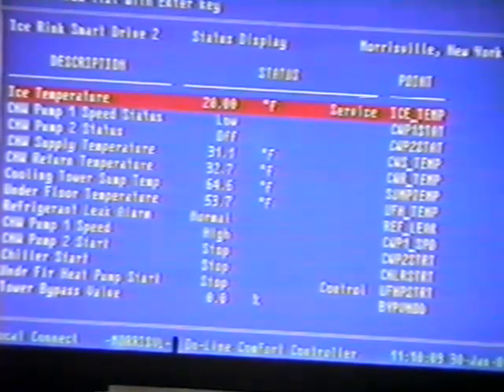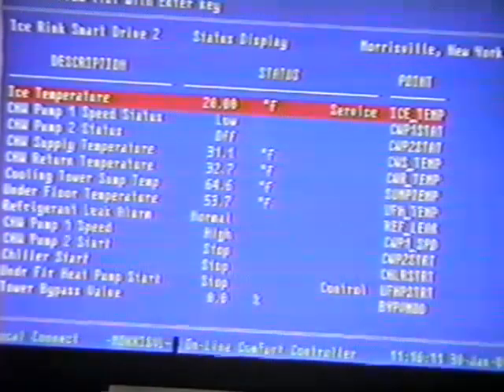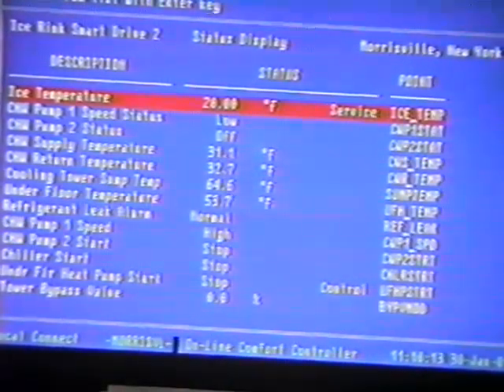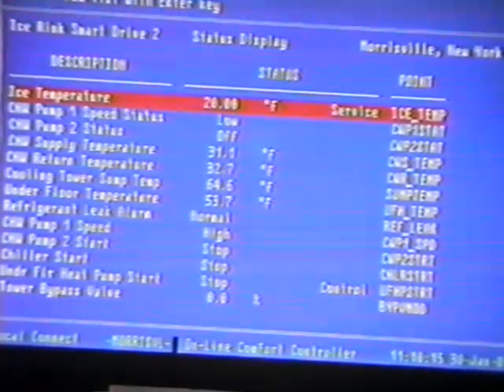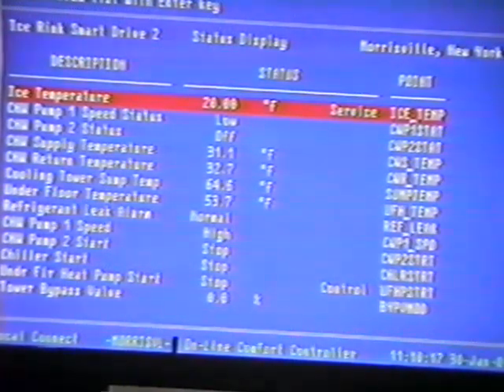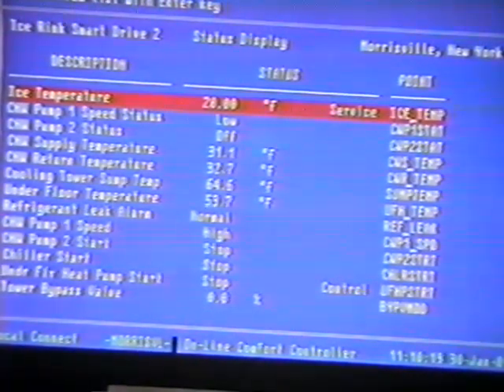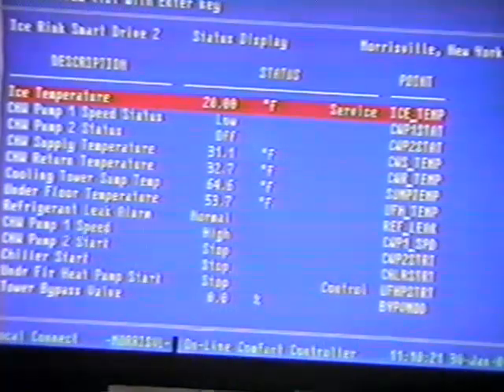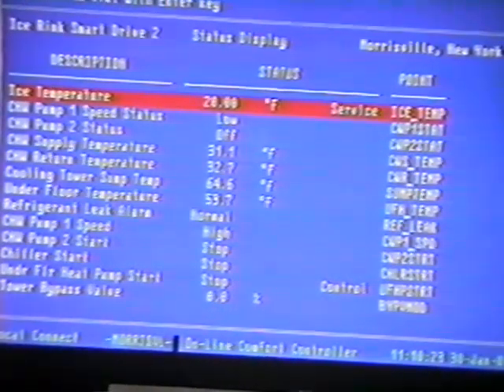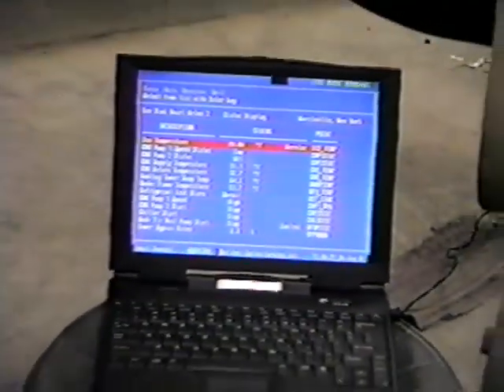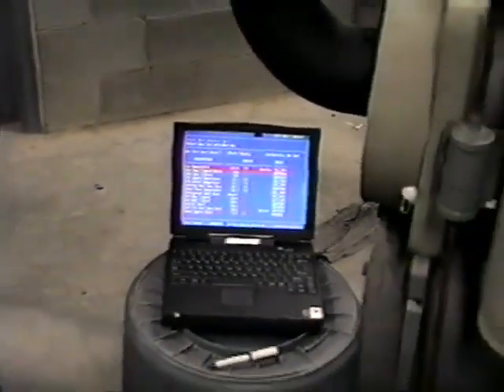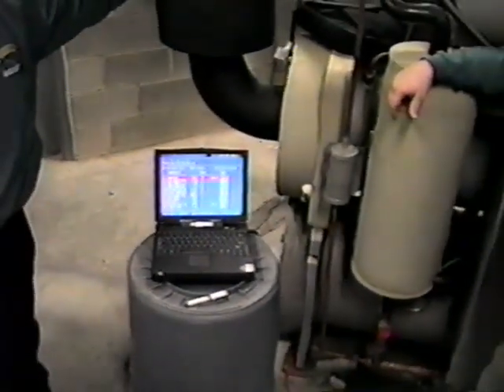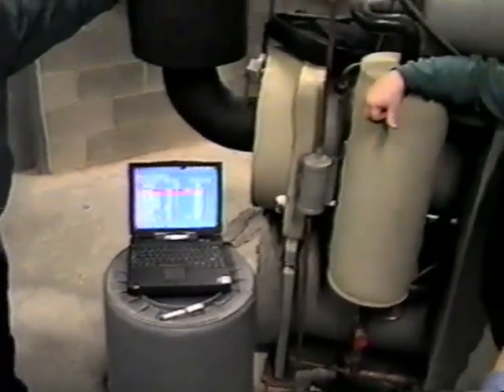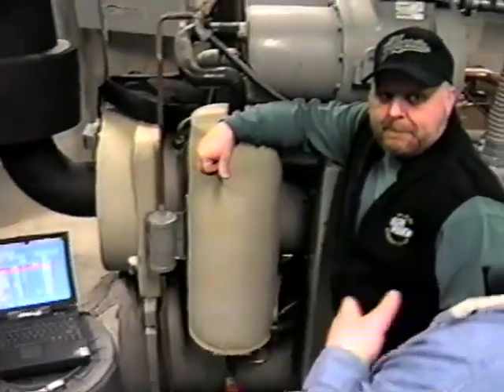If the ice temperature gets above 21, what you're going to do first is this thing's going to turn on the high-speed pump. The pump normally sits in low-speed dormant until you really need a call for cooling. It switches to high speed then, and on this thing we have a readback from the starter that proves that electrically we have gone to high speed. That's for protection of the compressors and that.